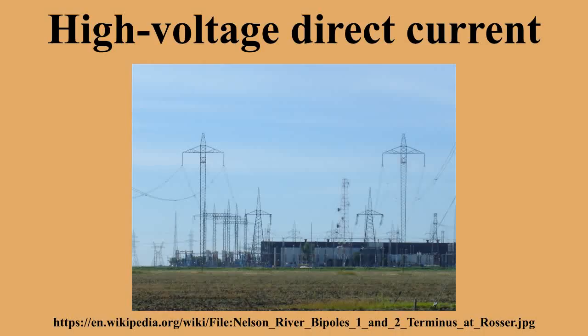The magnitude and direction of power flow through a DC link can be directly controlled and changed as needed to support the AC networks at either end of the DC link. This has caused many power system operators to contemplate wider use of HVDC technology for its stability benefits alone.